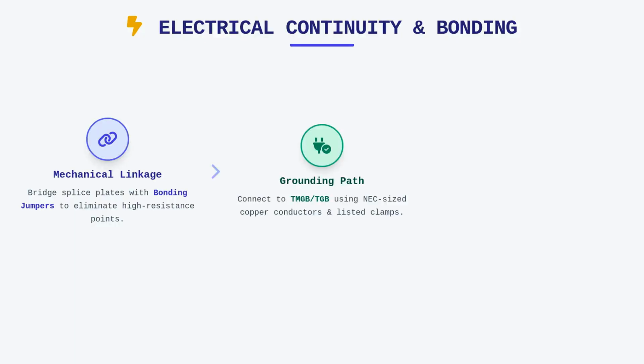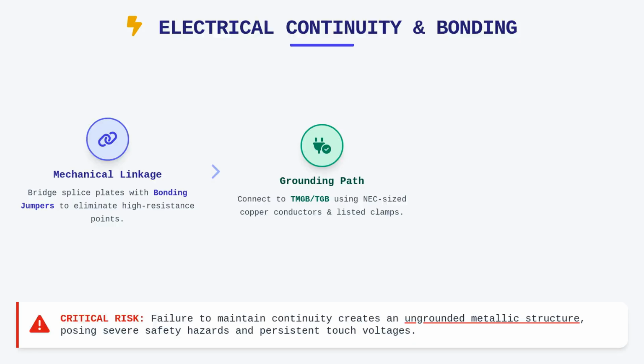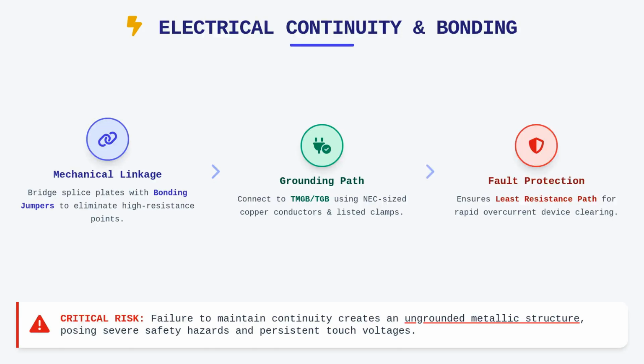Furthermore, you must attach these trays to the telecommunications main grounding bus bar or the appropriate telecommunications grounding bus bar using listed grounding clamps and copper conductors sized according to the National Electrical Code. Failure to maintain electrical continuity throughout the entire tray run essentially creates an ungrounded metallic structure, which is a significant safety hazard in the event of a power surge or a fault in nearby equipment. This grounding effort serves as a path of least resistance for potential fault currents, allowing overcurrent protection devices to clear faults rapidly and preventing hazardous touch voltages from persisting on the cable management infrastructure itself.